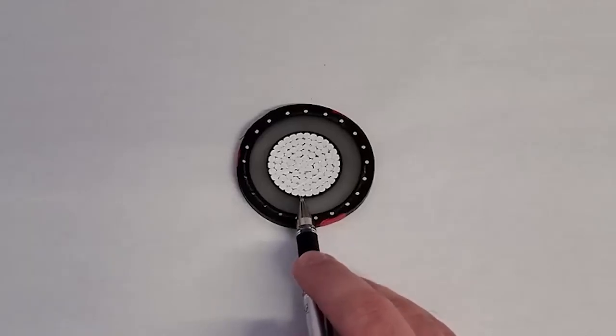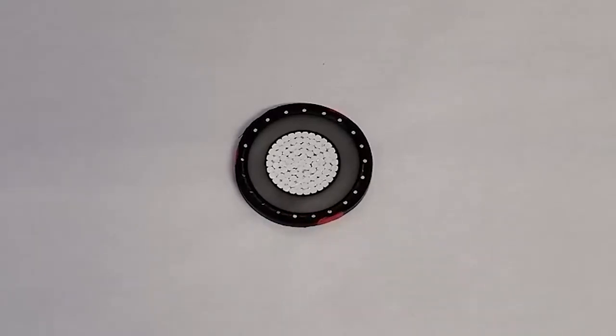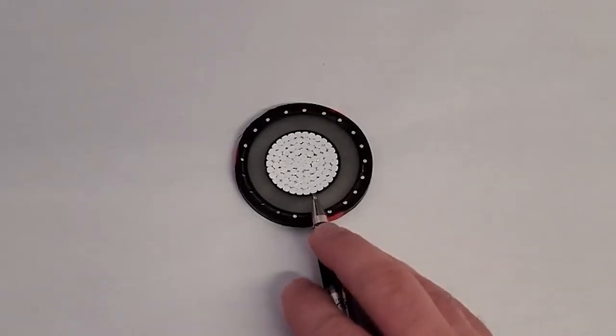And it's actually an XLPE type of polyethylene, but it's mixed with carbon black. I think the technical name for it is acetylene black. And it actually comes from a byproduct of acetylene. So you've probably seen somebody with an acetylene torch. When they first light it, you see a lot of that black smoke and black soot. The process of getting this acetylene black is capturing that and refining it. It's extremely conductive. So they mix that acetylene black with the XLPE insulation, and that's why it's black, obviously.